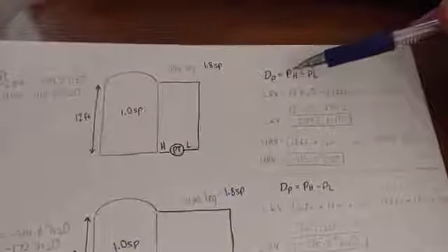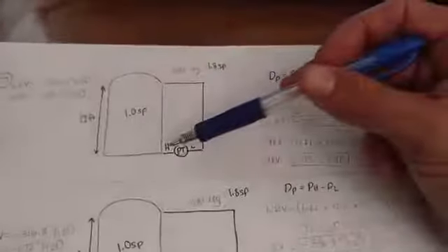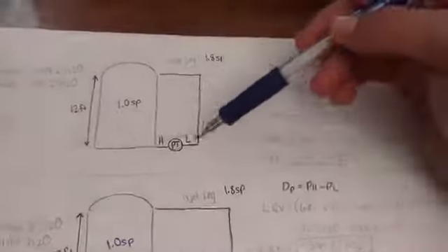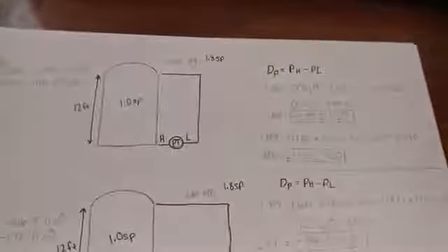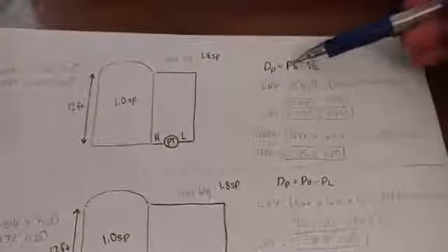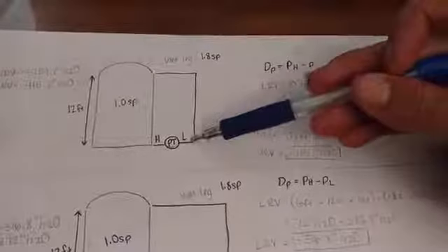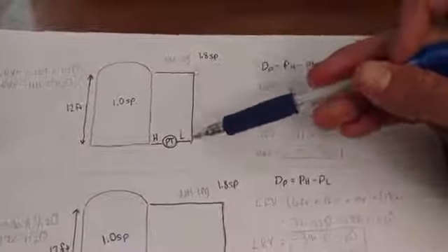What we're going to do is use this formula over here. This formula says that our differential pressure is equal to our pressure high minus our pressure low. So, for the lower range value, in this situation, we have 0 inches H2O for our pressure high side, because our pressure transmitter is actually even with the base of this tank, which would be at 0 feet of water. Okay, so we're going to have 0 inches H2O for our pressure high minus our pressure low side, which is going to be this hydrostatic pressure here.